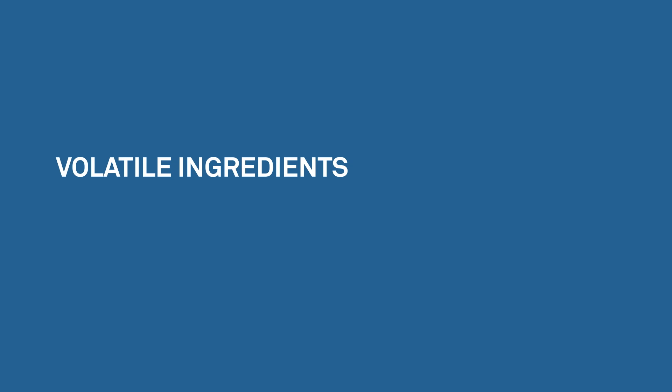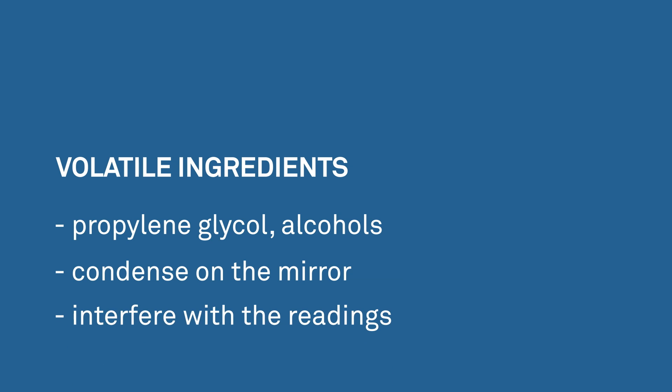There are a few ingredients like propylene glycol and alcohols that can cause issues with the mirror. The problem is that these volatile ingredients also condense on the mirror. When we heat the mirror up, they evaporate at a different rate than water and interfere with the readings.